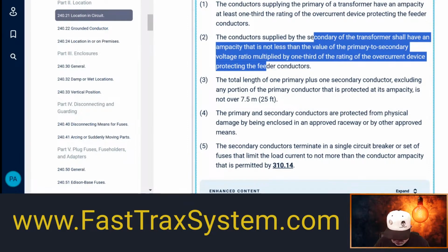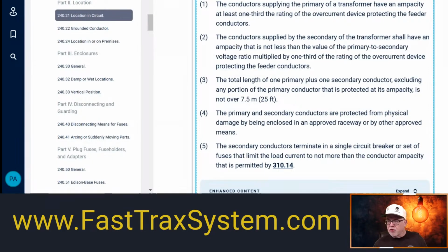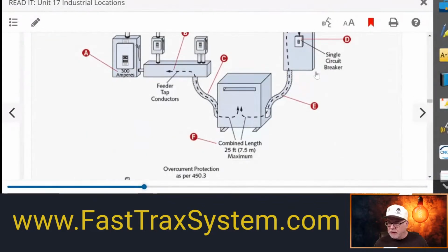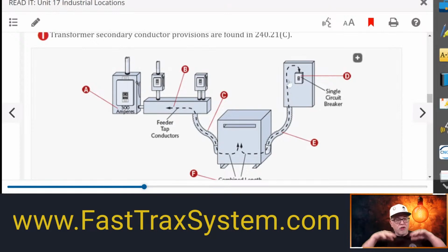Okay, and that was 300 amps, right? So 1/3 of that is 100 amps. So we have, in this case, 2.31 times 100. So that was going to be what? We have to have secondary conductors that are no less than 231 amps, okay? Because that would be the primary ratio multiplied by 1/3 the rating of the overcurrent, okay? So again, we didn't really have to do a lot of math there because it was 300 amps. So 1/3 of that is 100, so easy math. But in this scenario, this secondary conductor has to have an ampacity of at least 231 in order to use this rule.